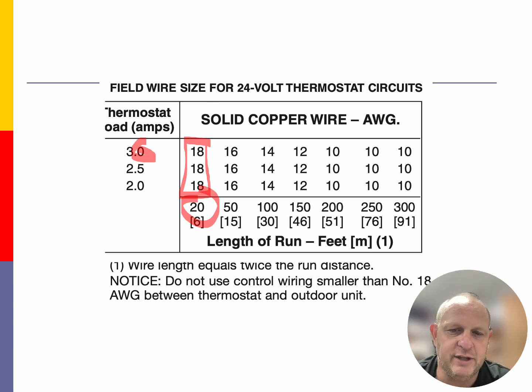It has provided for us. The voltage drop has not been significant enough for that 18 gauge wire to affect the operating system of it. But if we were going to follow manufacturer's recommended sizes for those particular units, then I would have to run some 14 gauge wire for that. And you're talking expense here for a control wire. So that's why we usually don't see a lot of control wires run in 14 gauge.